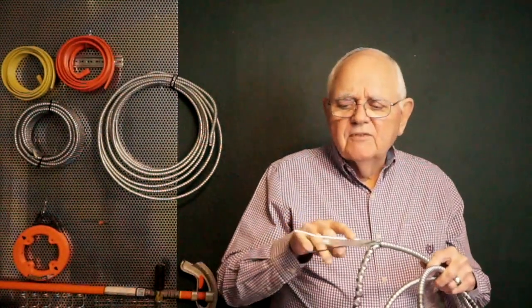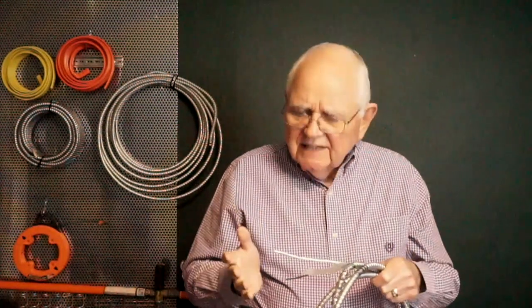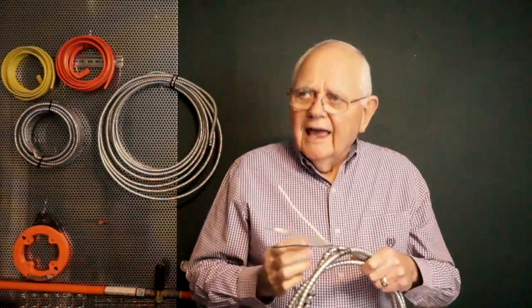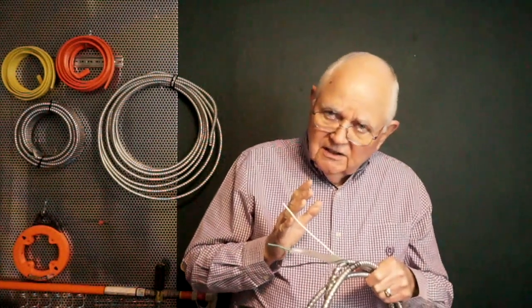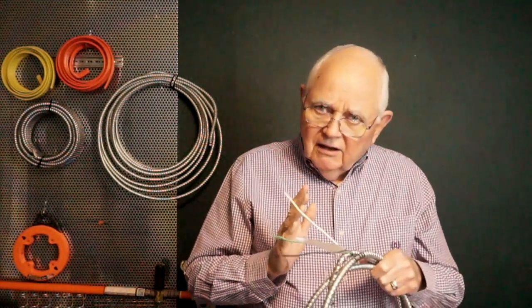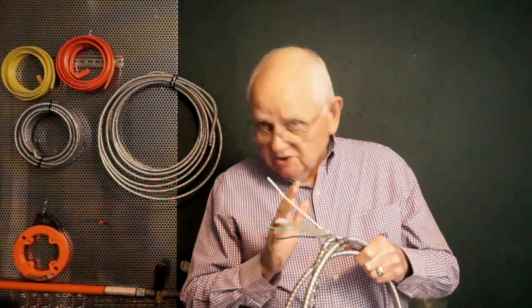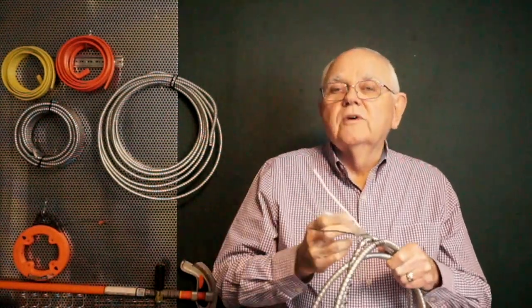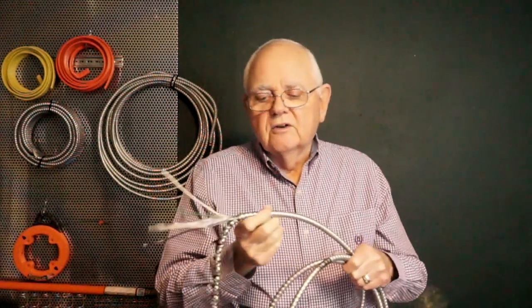Now, as far as the type of insulation, on most of the metal-clad cables that we work with, probably THHN or THWN is what we're going to use. However, in the smaller sizes, 18 and 16, you have to go to Article 402, which is on fixture wire. And there, table 402.3 lists all the different types of insulation for fixture wires, which would include the 18 and 16 when they're used inside of the metal-clad sheathing.